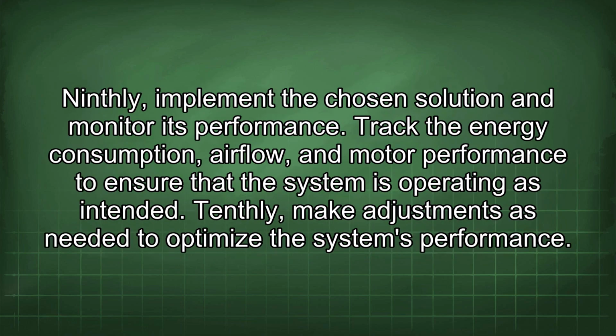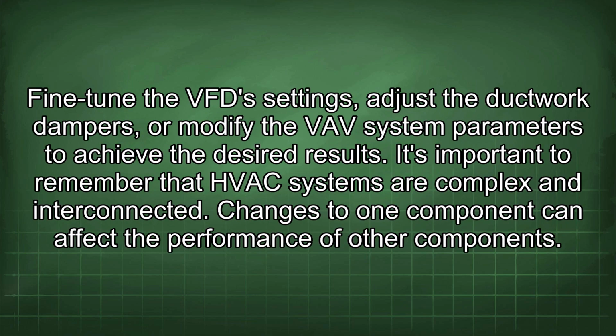Ninthly, implement the chosen solution and monitor its performance. Track the energy consumption, airflow, and motor performance to ensure that the system is operating as intended. Tenthly, make adjustments as needed to optimize the system's performance. Fine-tune the VFD settings, adjust the ductwork dampers, or modify the VAV system parameters to achieve the desired results.